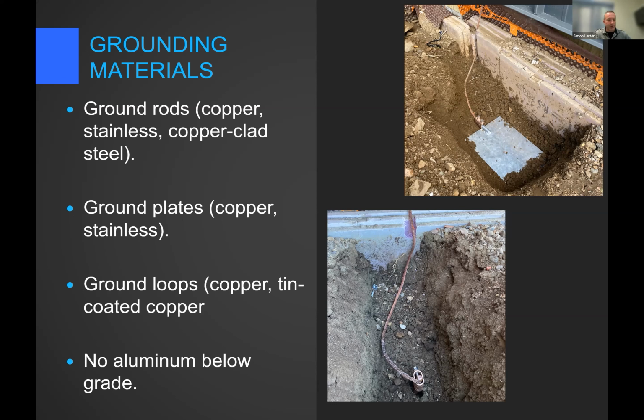Ground loops are going to be copper or tin-coated copper. The only material we do not use below grade is aluminum. That's because aluminum is going to corrode much faster in an acidic soil. In fact, by code, we want to keep aluminum about 1/2 meter up above grade. We want to make a transition to copper or tin-coated copper to go into the ground, 450 millimeters, 18 inches above grade per code. So aluminum does not go below grade. That's the only material we do not use down there.